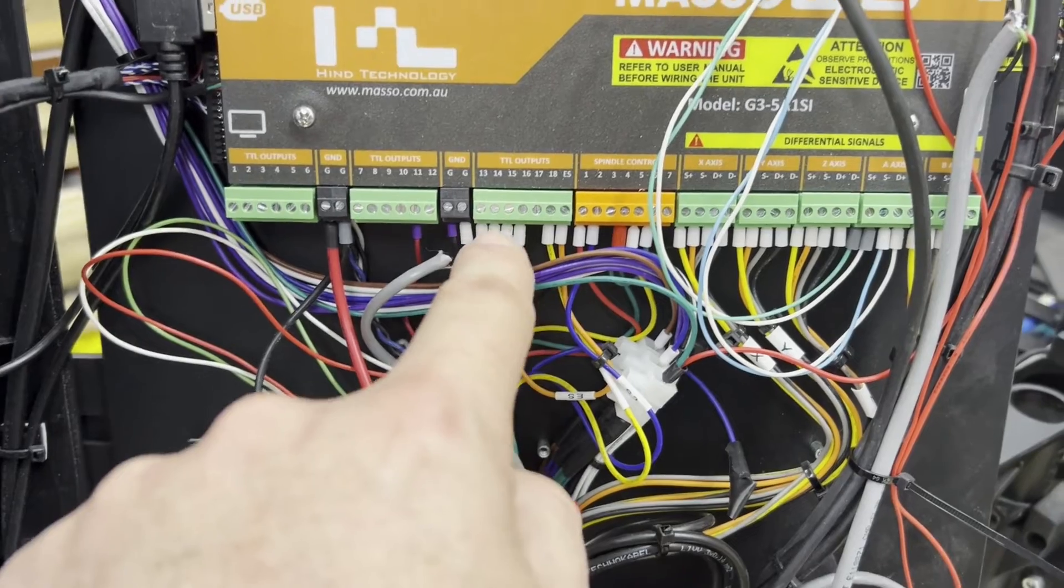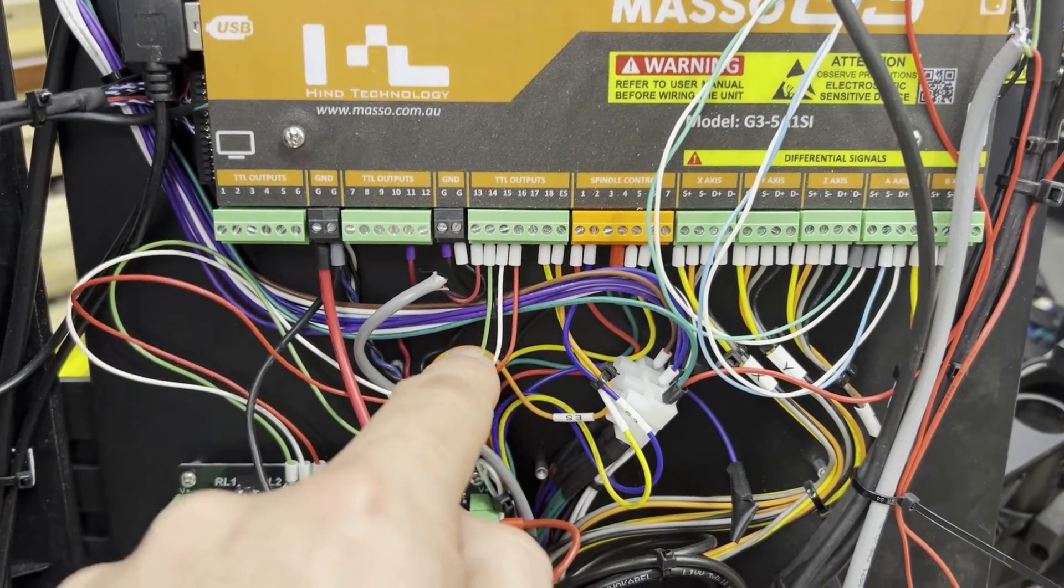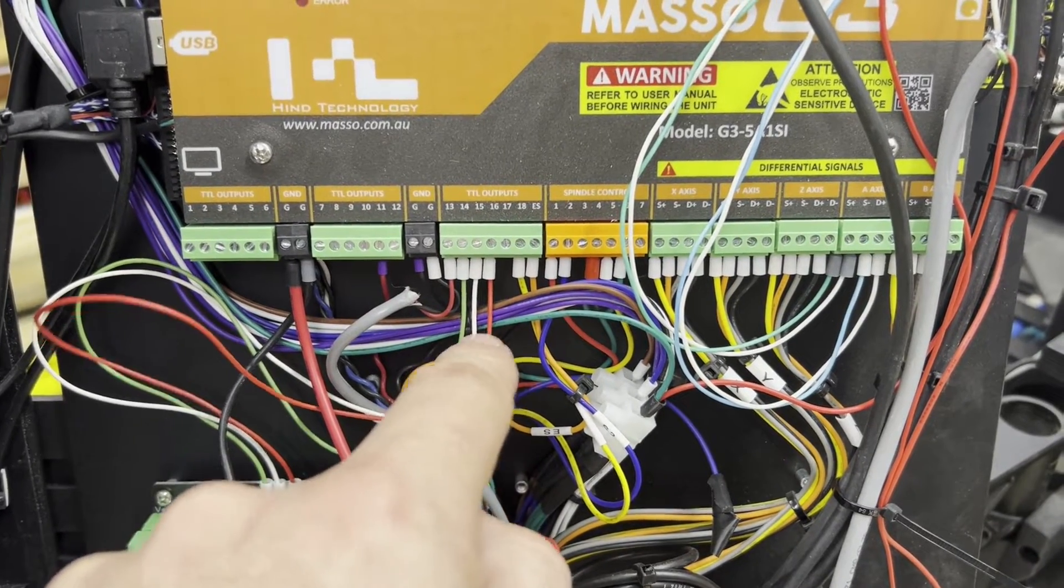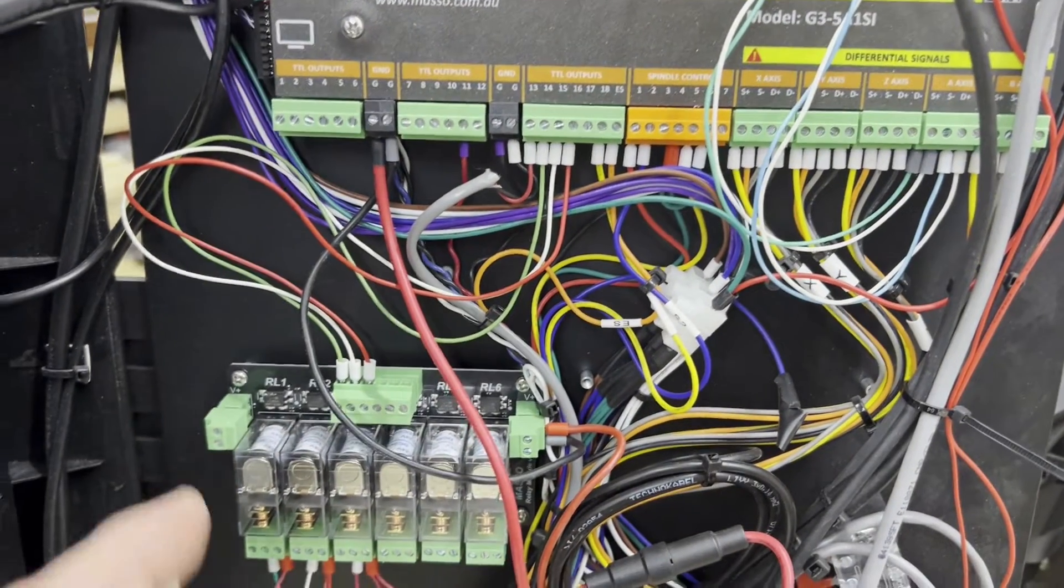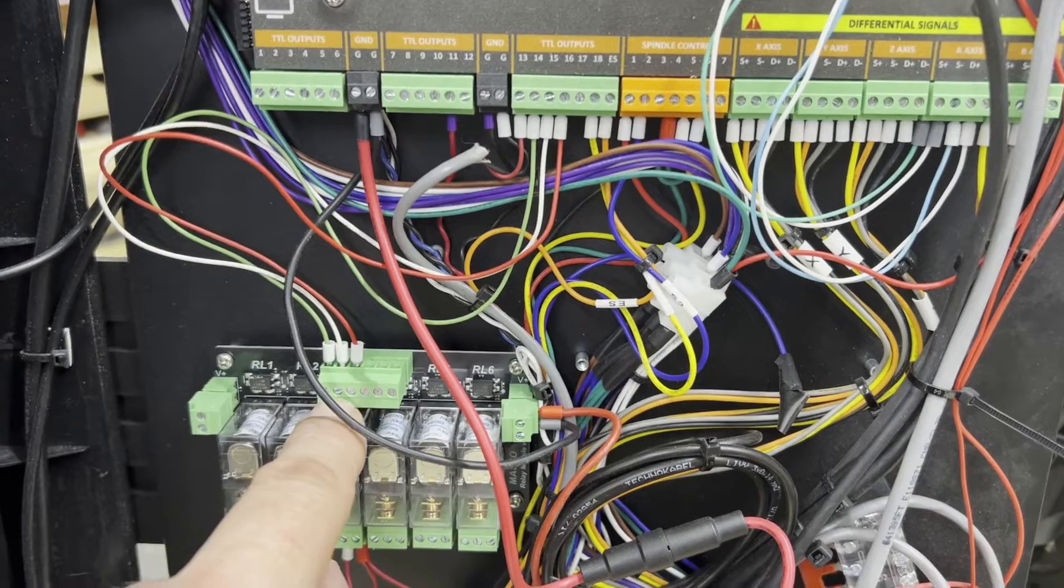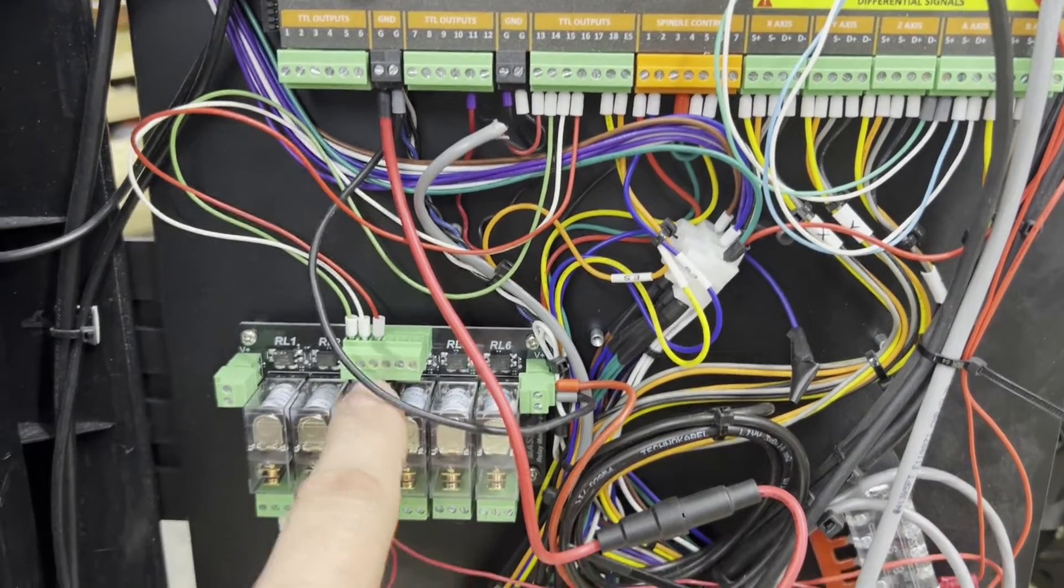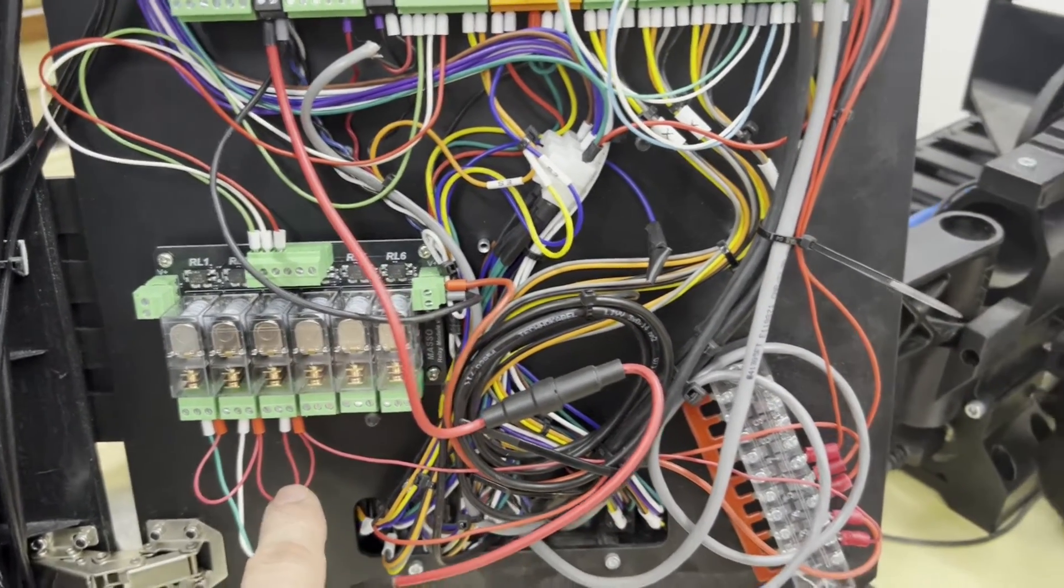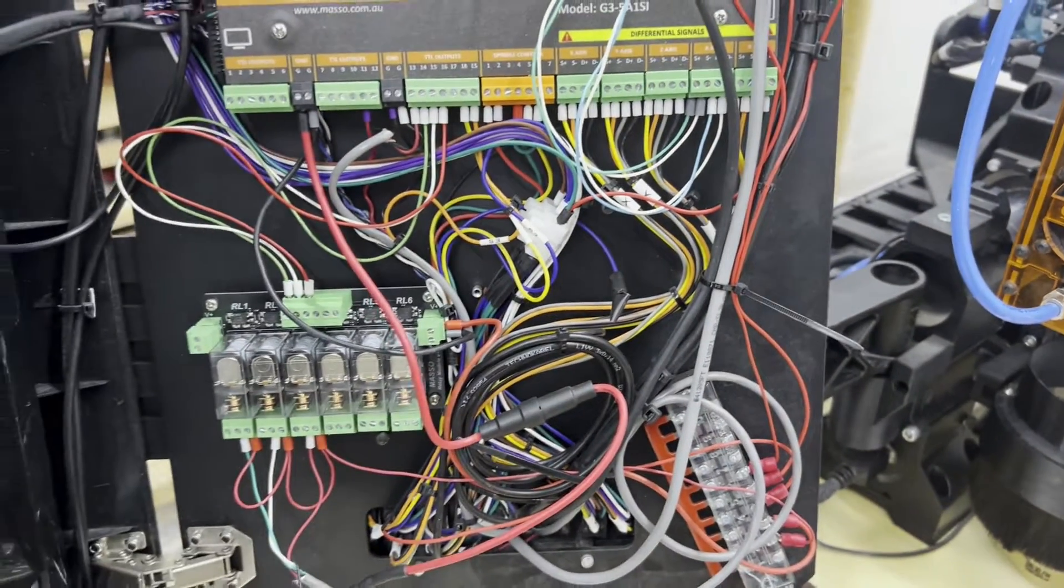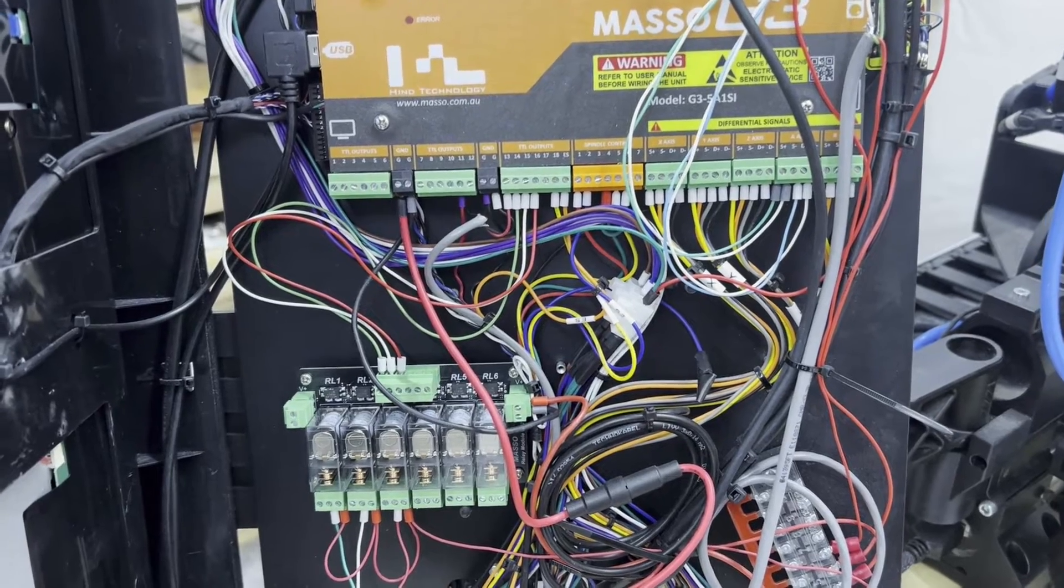We just now need to connect the controller to the relay, so it can trigger the right alarms at the right times. So, I'm going to use TTL outputs 14, 15, and 16 for green, yellow, that's the white wire here, but yellow alarm, and red alarm. And I'm going to, again, put these in sequence, green, yellow, red, for my triggers, to trigger the green, yellow, red outputs. And that is all there is to it. We have it wired up. Let's take a look at the tower light.